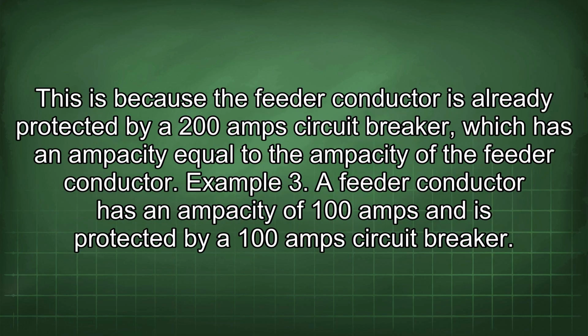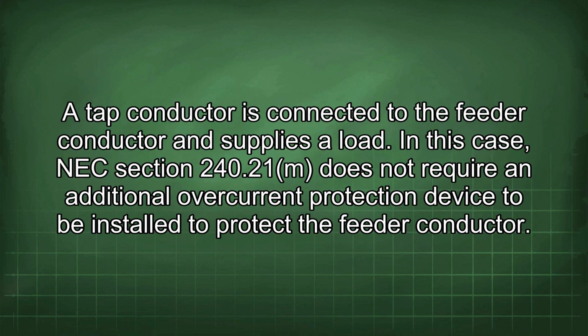This is because the feeder conductor is already protected by a 200 amp circuit breaker, which has an ampacity equal to the ampacity of the feeder conductor. Example 3. A feeder conductor has an ampacity of 100 amps and is protected by a 100 amp circuit breaker. A tap conductor is connected to the feeder conductor and supplies a load.